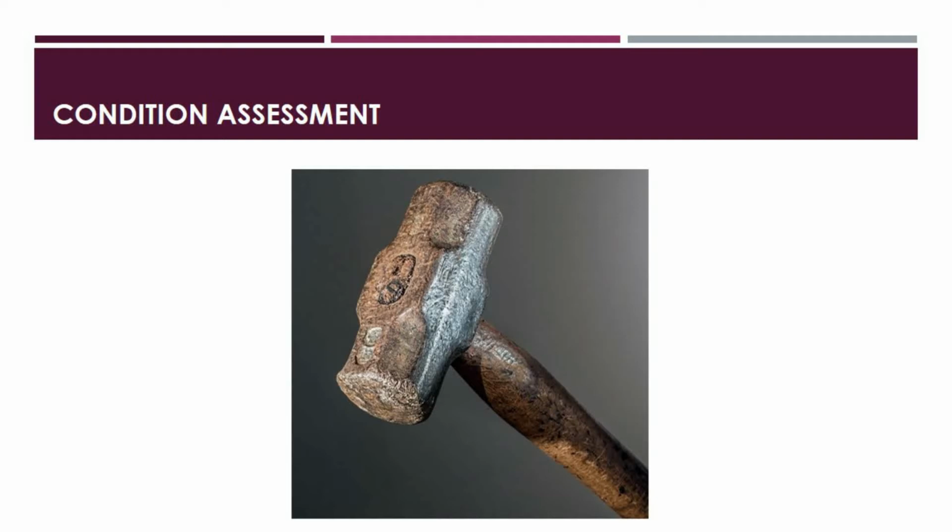Clearly, these simple tests are subjective, but they are quite useful for detecting wood degradation and identifying questionable poles when performed by competent personnel. In many cases, power companies have utilized similar techniques to evaluate if poles are nearing or have reached the end of their useful lives, as well as the necessity for pole replacement.